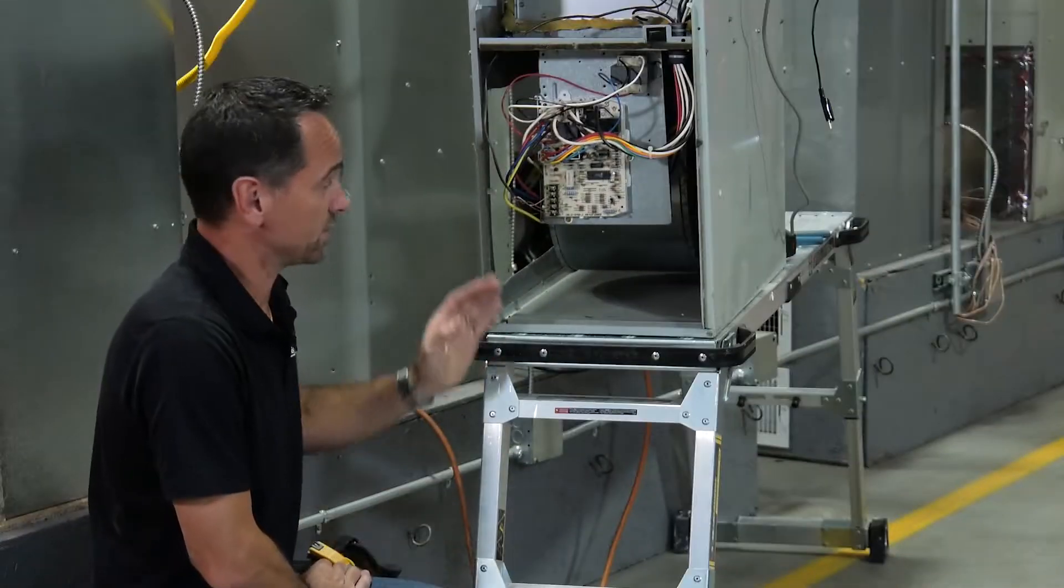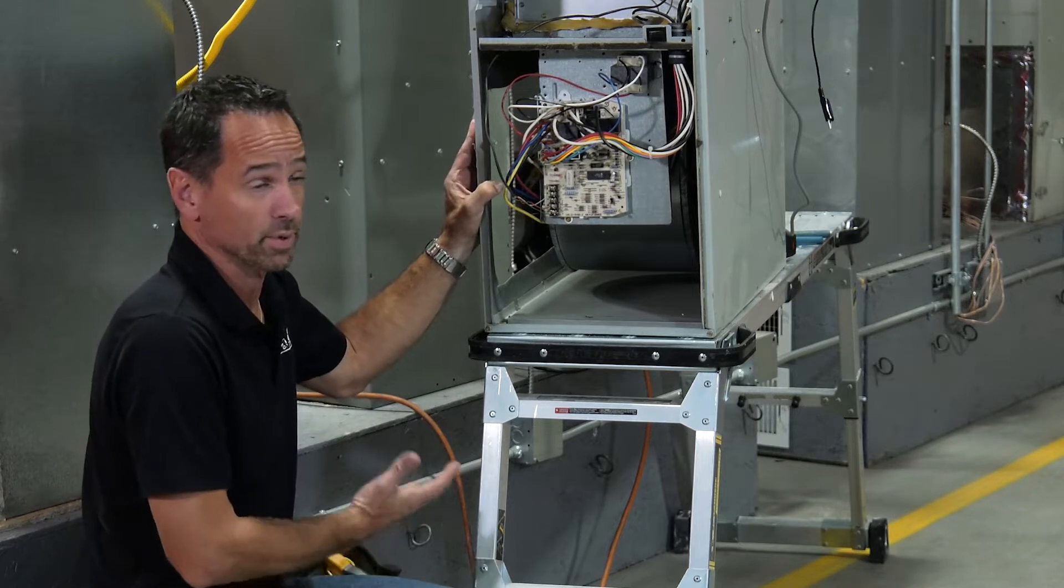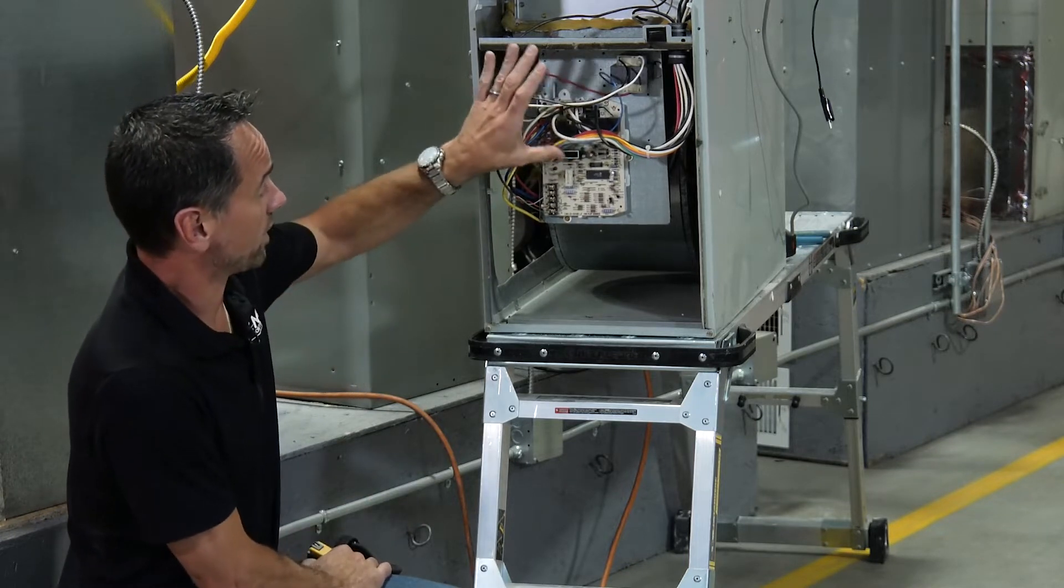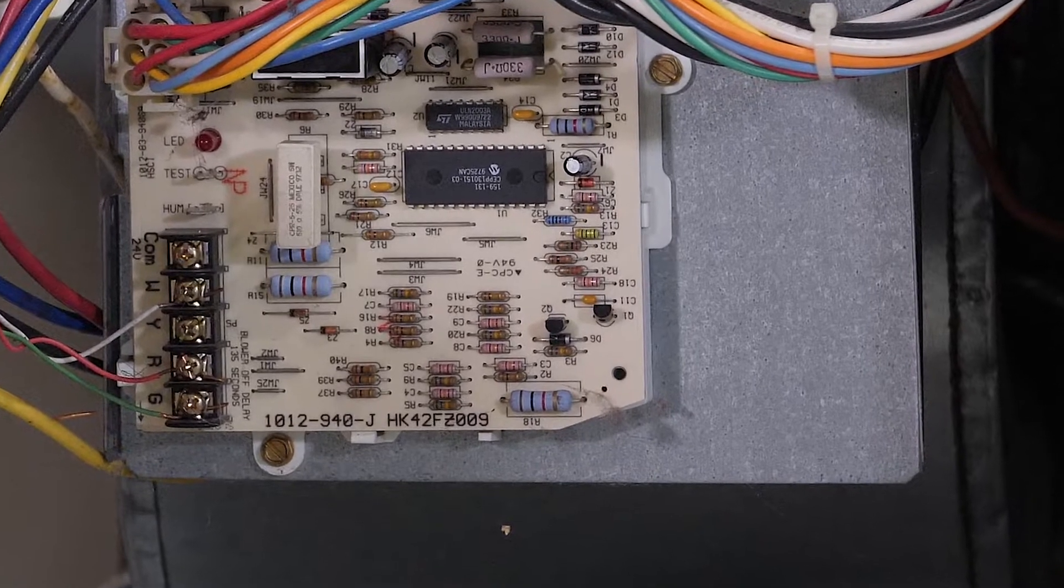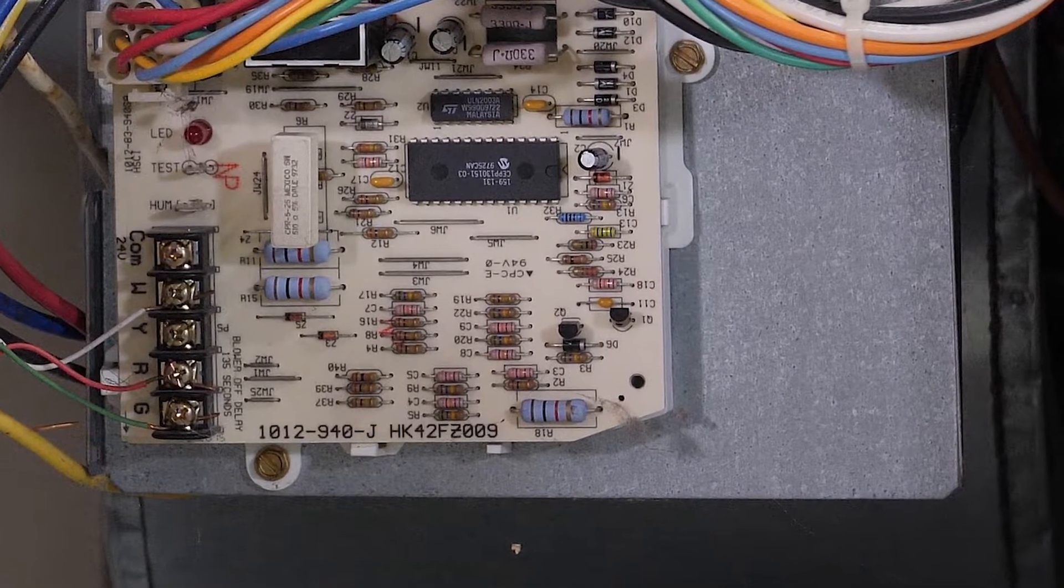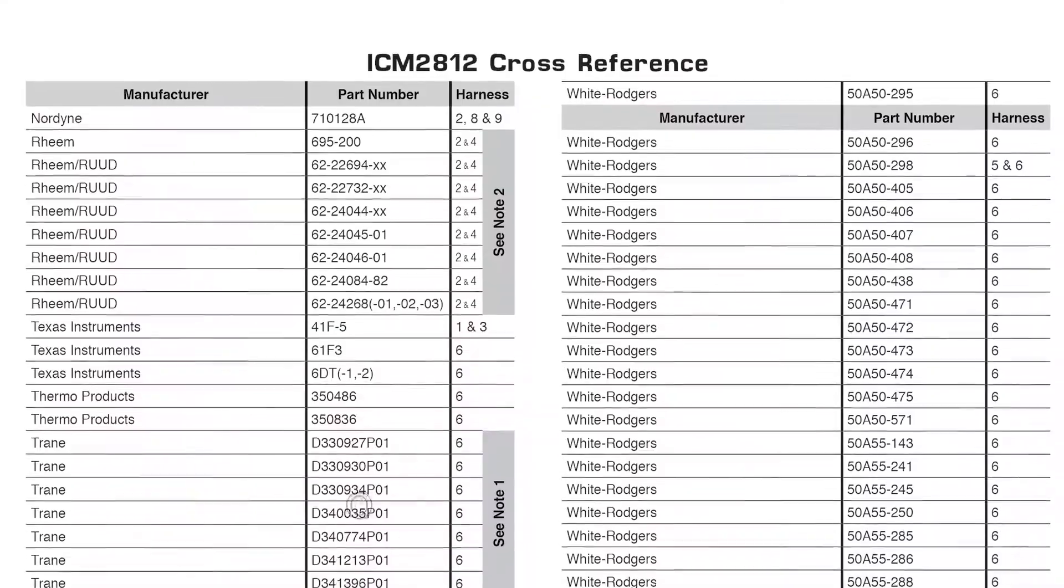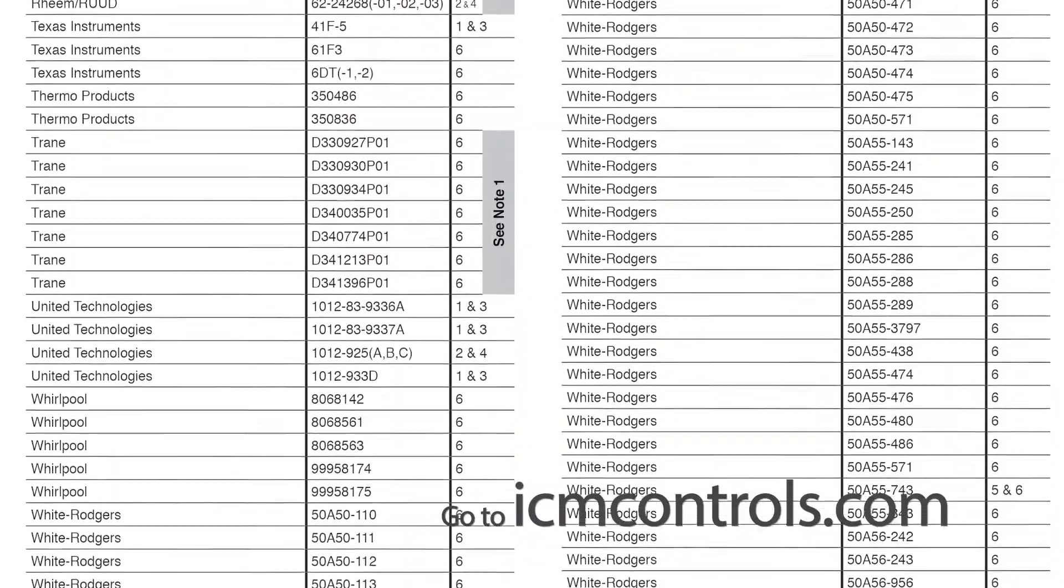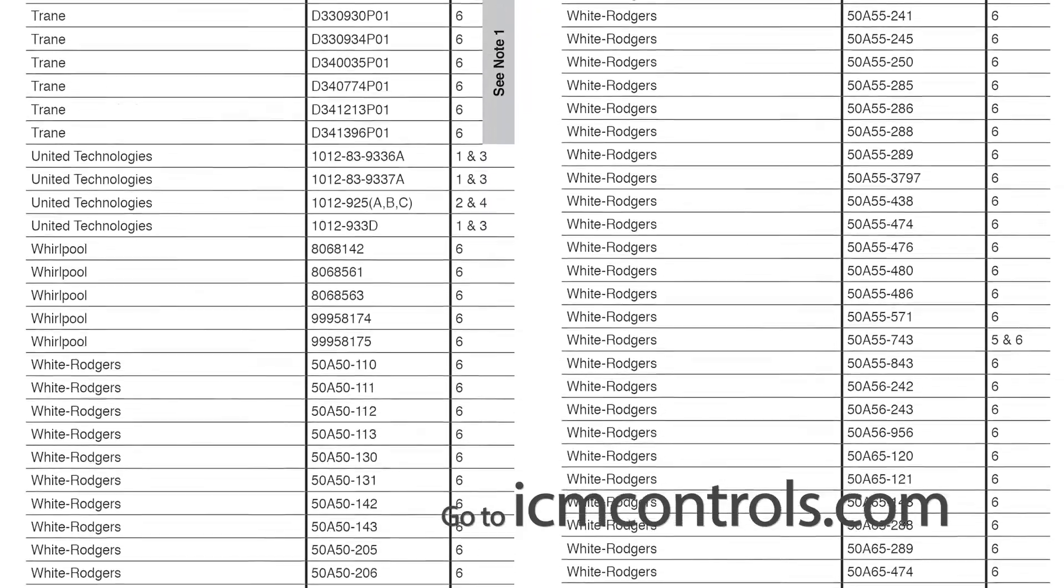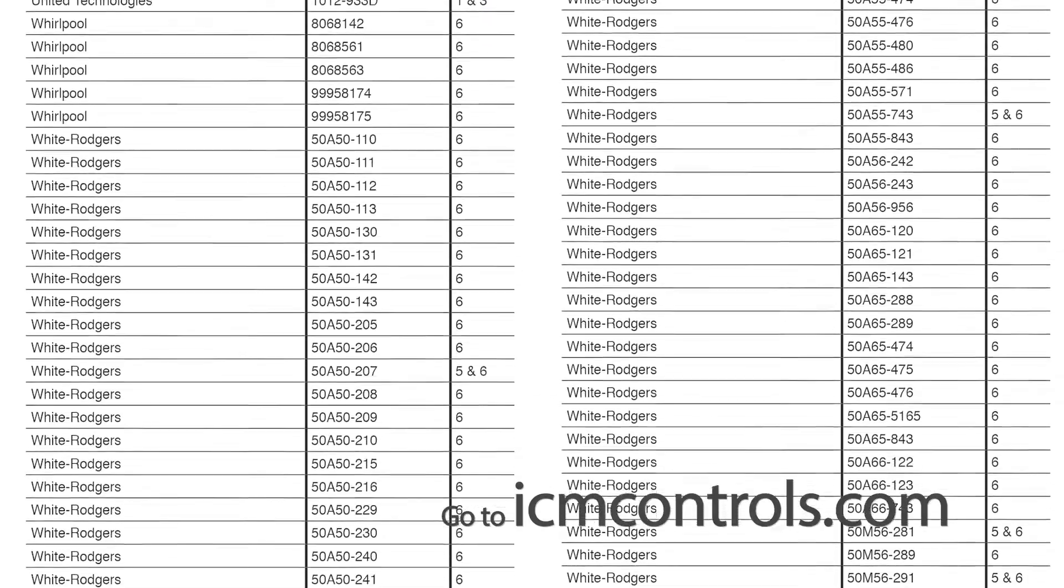So what we're working on today here is a Payne furnace, which is a Carrier product. We already went ahead and figured out which board we have, and it's going to give us a model number HK42FZ009. So what we're going to want to do is take that part number and either go to icmcontrols.com and check the cross reference or pull out the installation manual right out of the box.